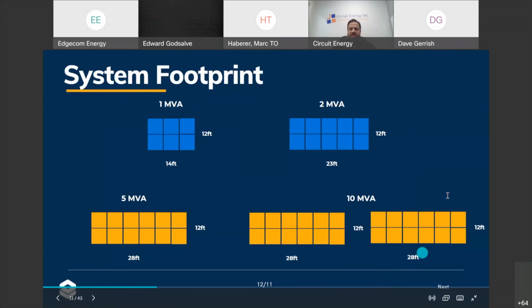So to give you an example, let's say a 1 megawatt system would have 6 cells in it. Each cell is about 225 kilowatts, and they take about 4.5 by 6 feet of space. If we put them all together at about 10 feet high, side by side, as a two-dimensional top view, a 1 megawatt system will be 12 feet by 14 feet in size. A 2 megawatt would go to a 12 by 23.